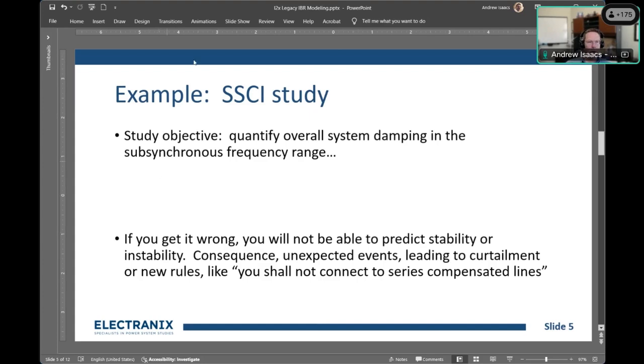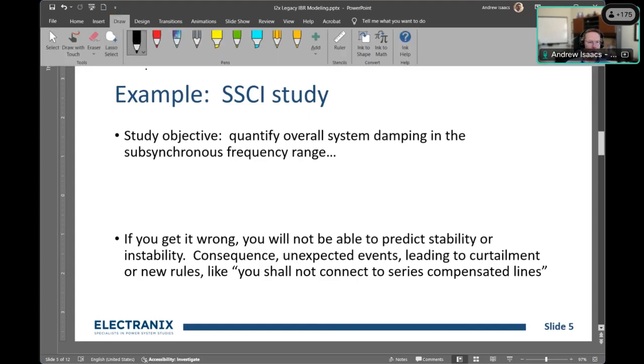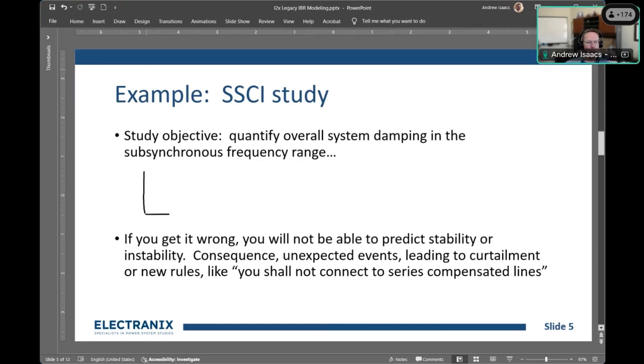We can do that with a frequency scan of the impedance versus frequency. Around 60 hertz, we'd look at resistance in a simple way—there are more complicated scanning methods—but we're looking for regions in the subsynchronous frequency range where we see negative resistance, which would indicate the plant might have negative damping at some frequency, say above 30 hertz.